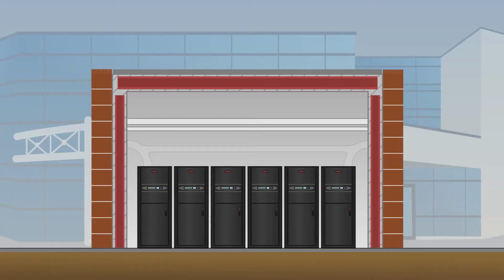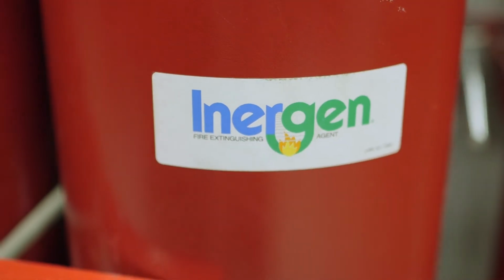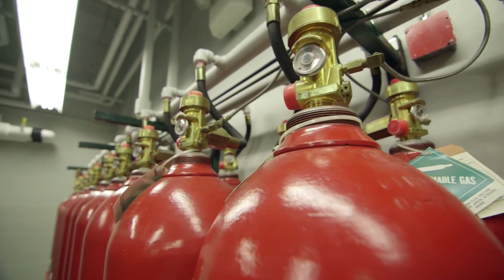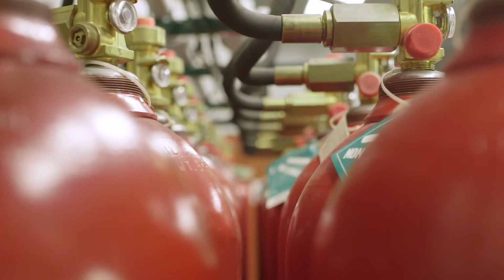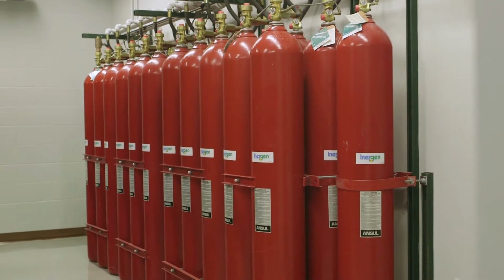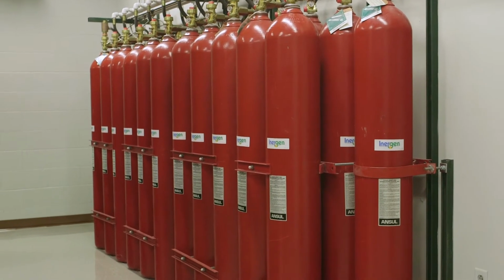First, this room and the operations center as a whole were set up with 1-foot-thick steel-reinforced concrete walls, along with an 8-inch steel-reinforced concrete slab roof. When designing this building, the specifications to withstand a direct hit from an F5 tornado were effectively doubled. Additionally, we also have Inergen fire suppression throughout this room and the facility. This is the environmentally friendly replacement for halon, so it's easy on the electronics and easy on the environment.